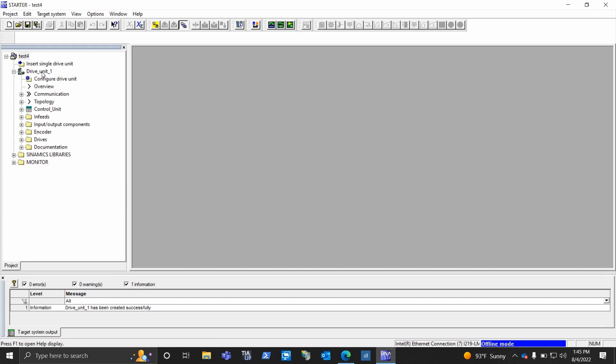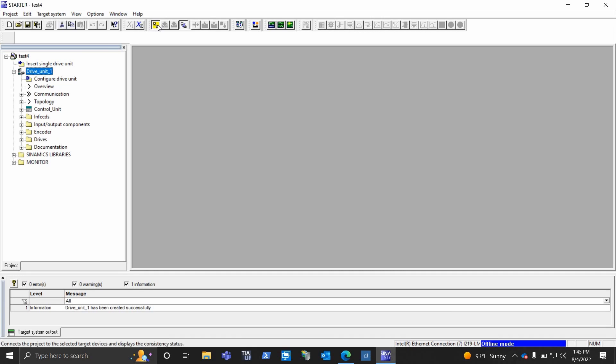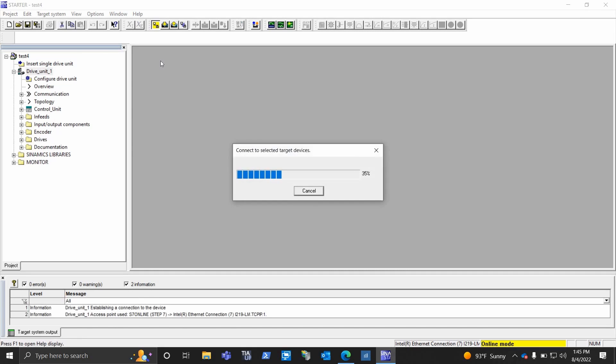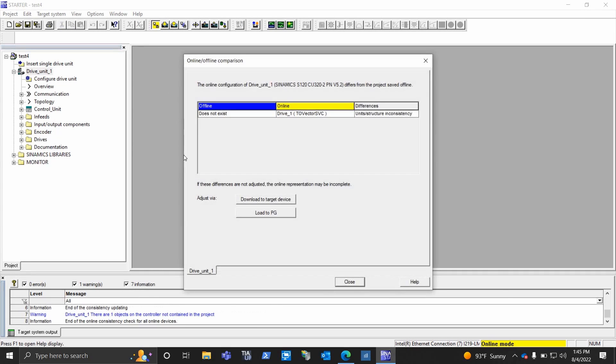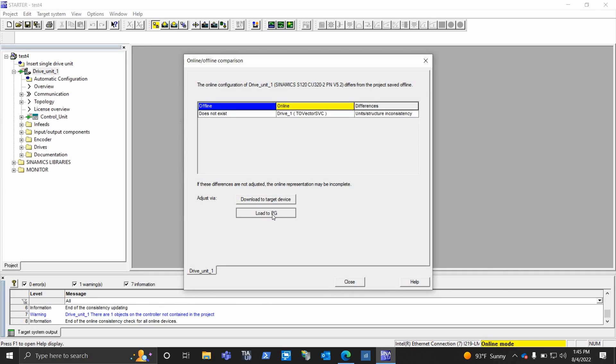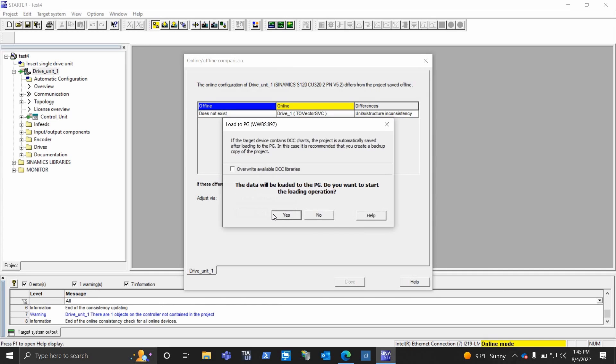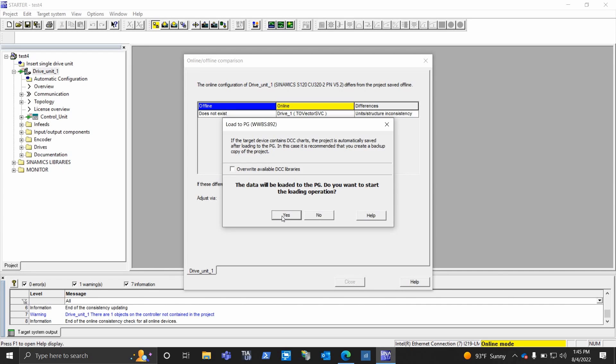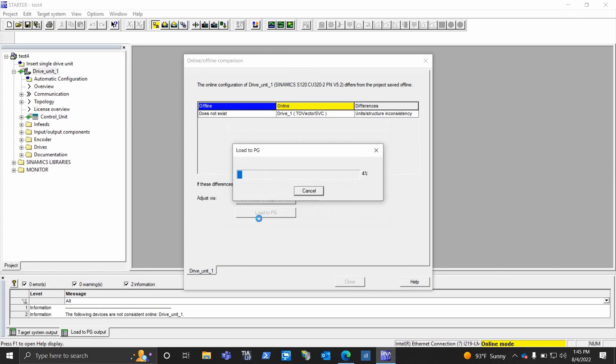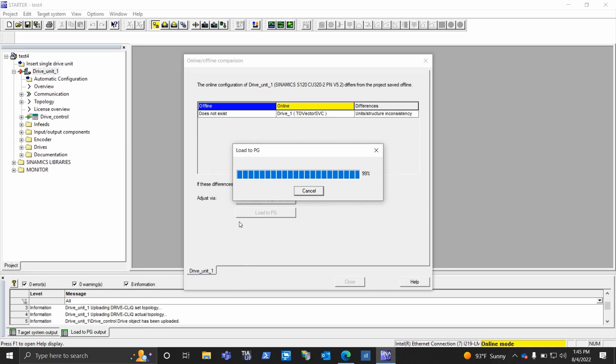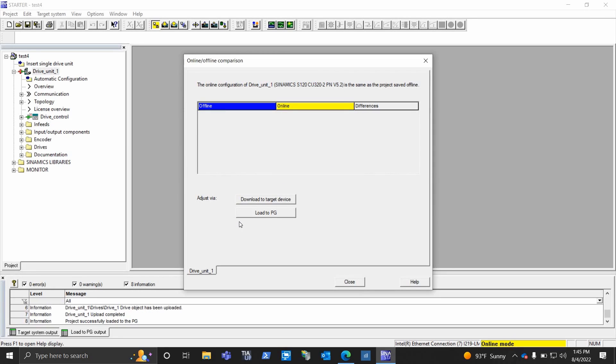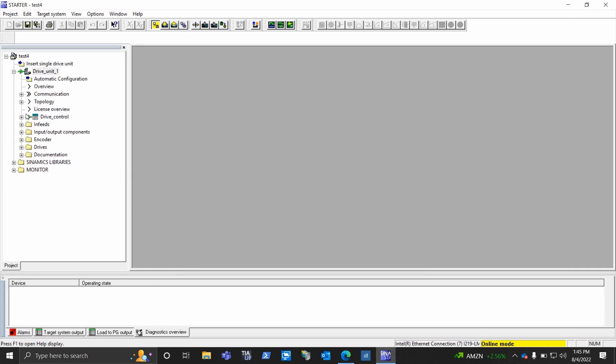Now I'm going to go online because I want to make sure I upload to the PG, which is your computer. PG is a PC. And I'm going to load all the parameters, so I want to back up everything before I start messing with the settings. And normally I'd also save this as some other file once I've uploaded it, so that I know, don't mess up the original upload for backup.